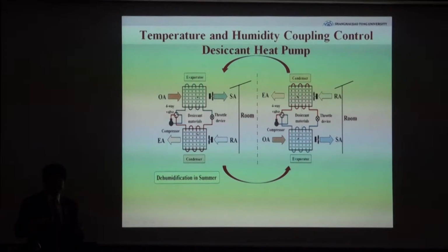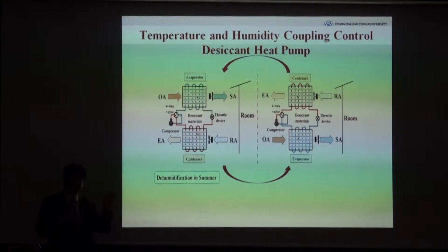But you need to work out how to regenerate the desiccant materials on the condenser. If we have a 15 degrees evaporating temperature, the condensing temperature could be somewhere between 45 and 50 degrees centigrade. Originally, this condensing heat was rejected to the ambient air. Now, this condensing heat could be partly used for the regeneration of desiccant materials. The desiccant material, once it becomes wet and absorbs a lot of moisture from the air, needs to be regenerated. So in this case, what we could do is just have the evaporator and the condenser change phase.